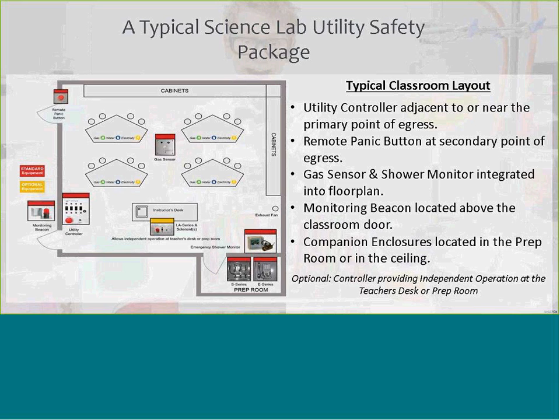You also have a fuel gas sensor. Fuel gas sensors are really good because if the room starts to fill up with gas, that will shut the system down and make sure that the unit cannot be reset. As long as that is sensing gas in that room, the unit will be shut down. The electrical and water will also be shut down as well. The other thing, again, that we talked about is shower monitoring. With a shower monitor, if someone were to pull the emergency shower, which is 20 gallons a minute, which can flood pretty quickly, then we can send a signal to the control panel, and from the control panel we can send a signal out to the fire alarm or the building administration through the controls of the energy management system to let them know that the shower is active.